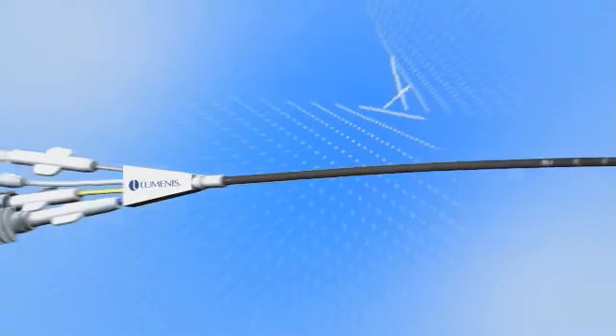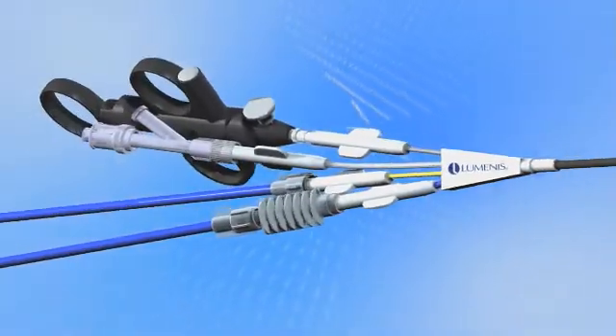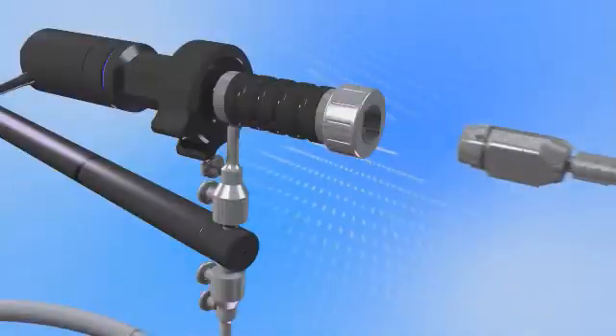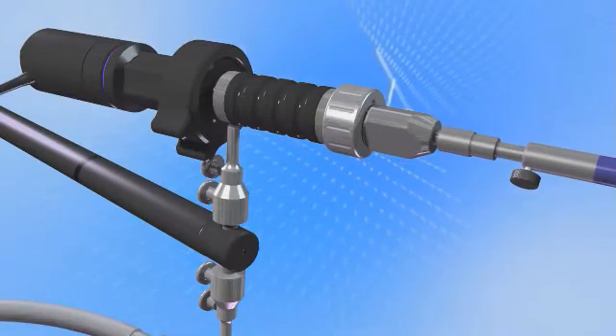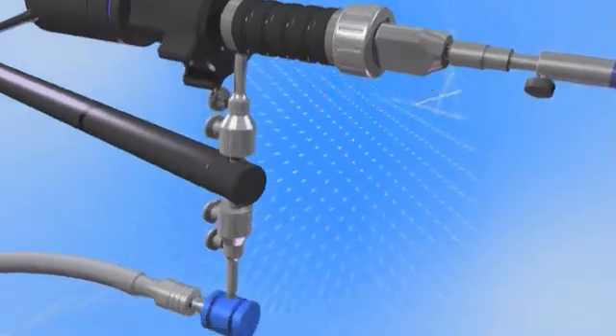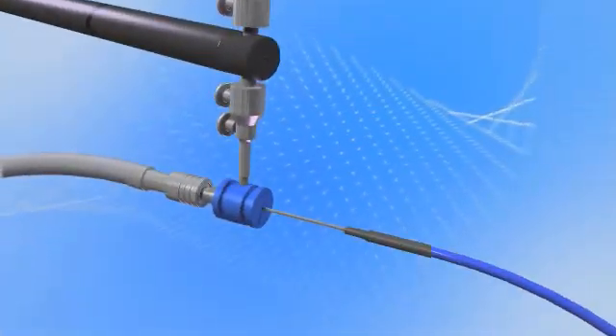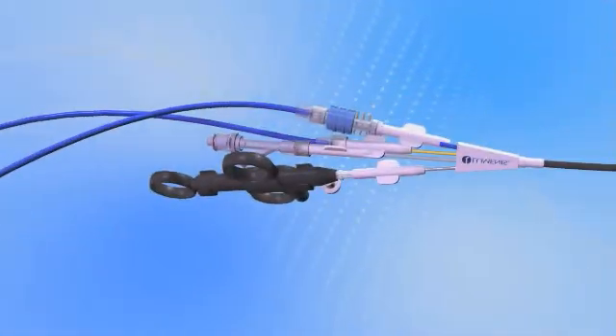The PolyScope is attached to the imaging system with 2 simple connections. The fiber optic is connected to the ocular, and the lighting channel is connected to the light cable adapter. The PolyScope is now ready for use.